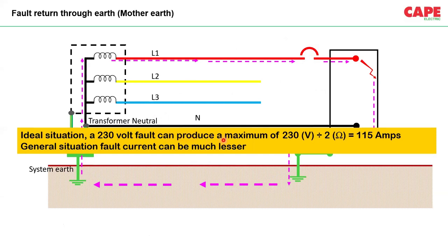So in an ideal situation, a 230 volt fault can produce a maximum of, let's say, 230 volt divided by 2 ohms, about 115 amps. But the ideal situation will never happen. In a general situation, the fault current will be much lower. It may sometimes be 10 amps, 20 amps, something like that, very, very less. In a TT network, fault current can never be higher.